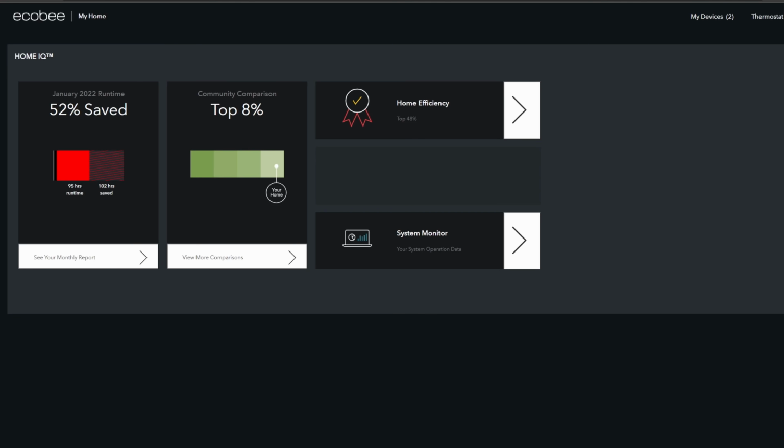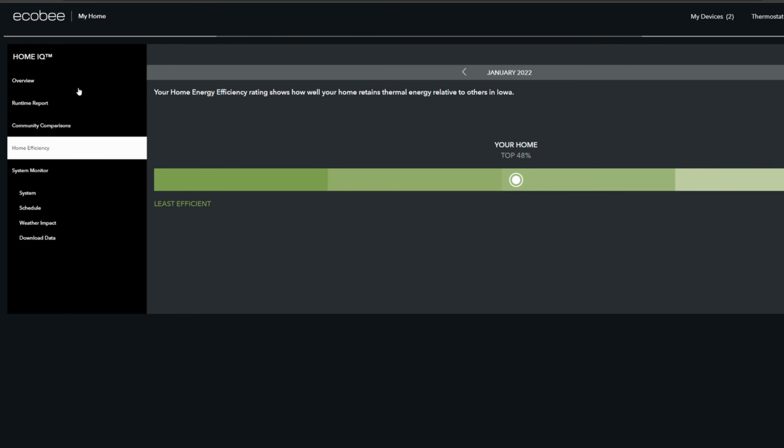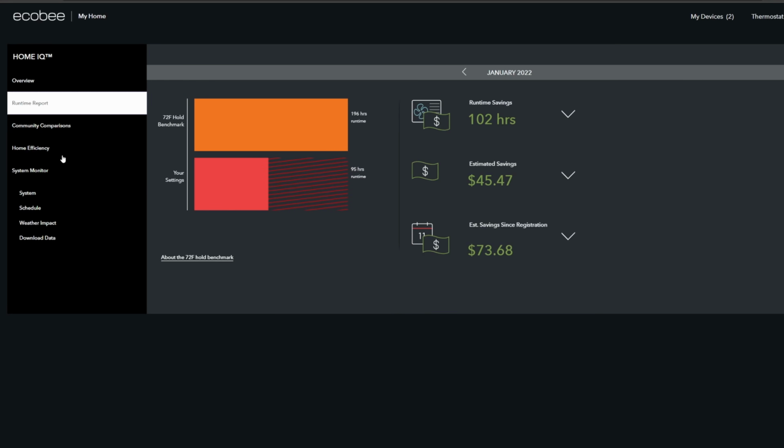But the most important thing I want to show you is right here. It says 95 hours of runtime. That was the entire runtime for the month to heat the garage at 45 degrees as a set point. Let's hop in here and look at the data. So again, the runtime report is showing 95 hours of runtime.